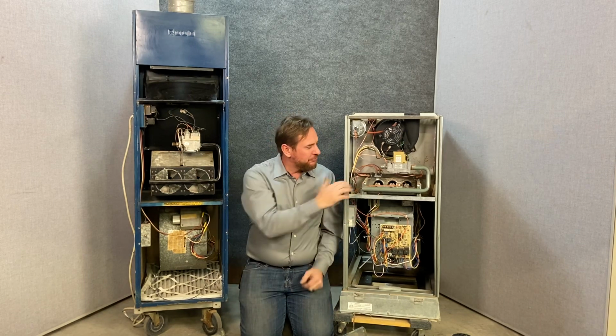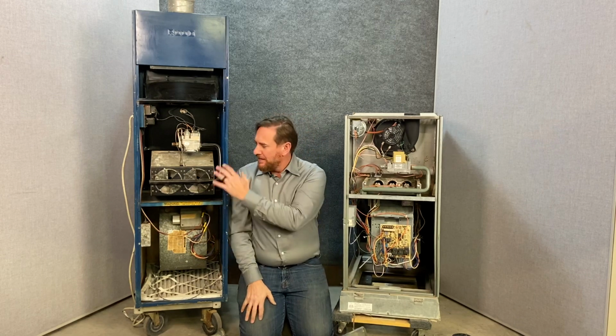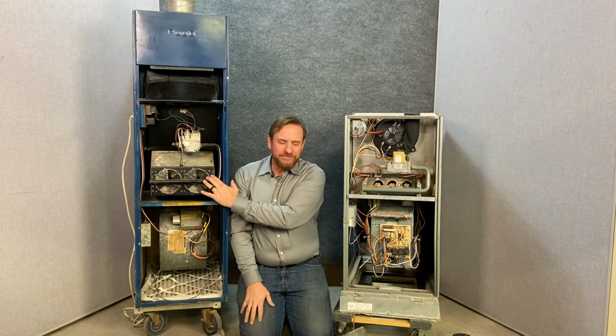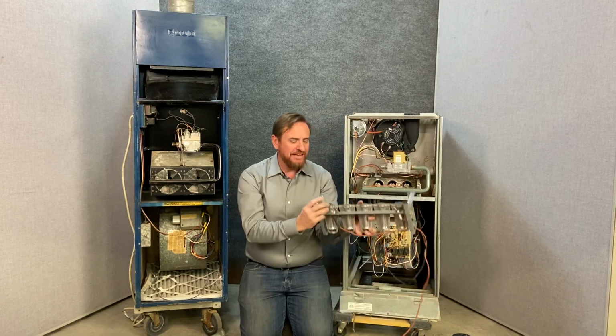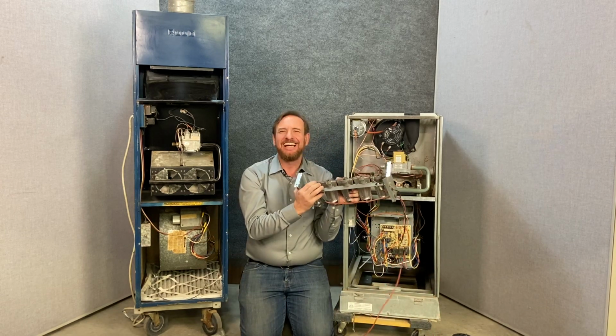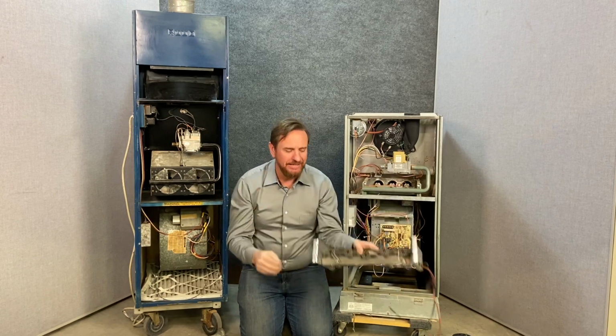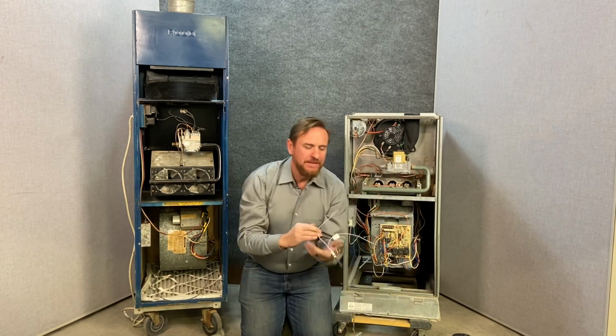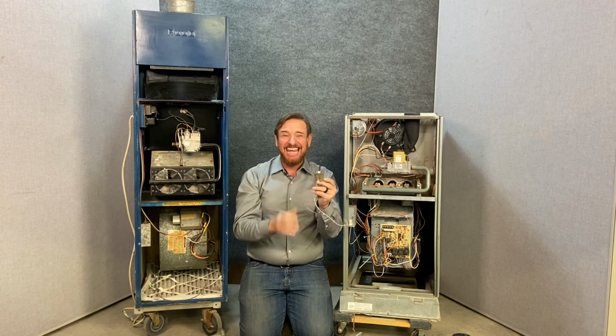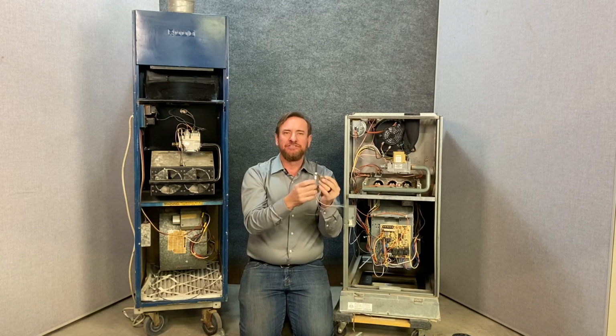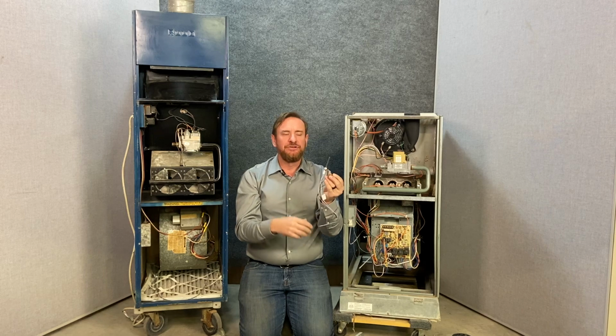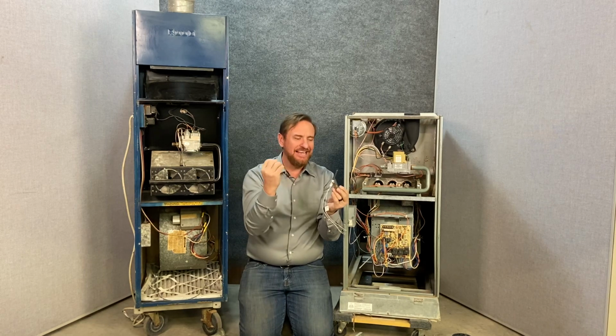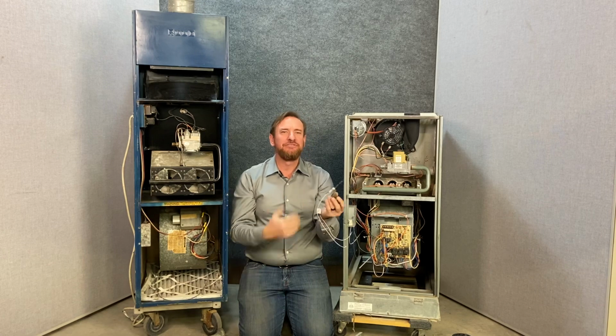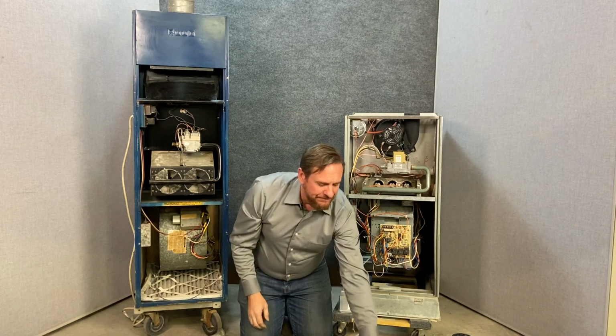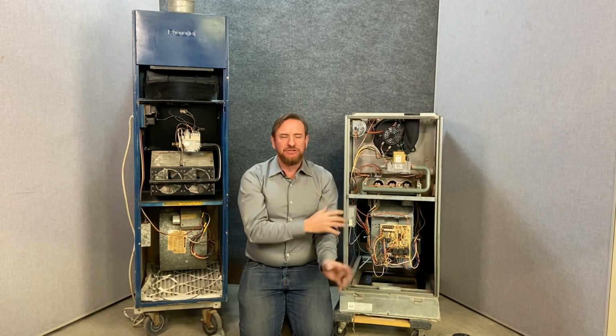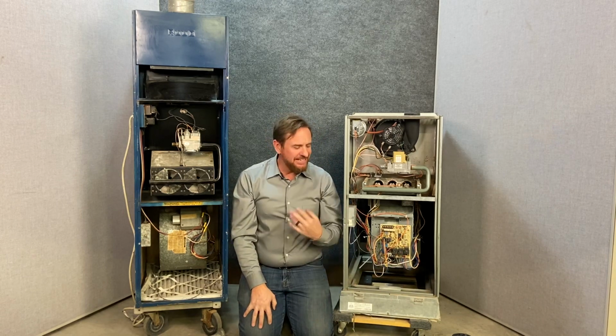So this one has the protections for that, this one doesn't. This one over here has a pilot light that burns all the time, and this one is going to have that spark igniter, so it's going to spark and ignite the main flames directly, immediately. Now, some companies also use a hot surface igniter called an HSI. These are also very popular. It sends 120 volts to them. This gets extremely hot, and then as the gas comes across this igniter, it ignites into a flame, burning in the heat exchanger. So, very efficient. A lot safer, this new model. But let's talk about the heat exchanger. I've said heat exchanger several times.